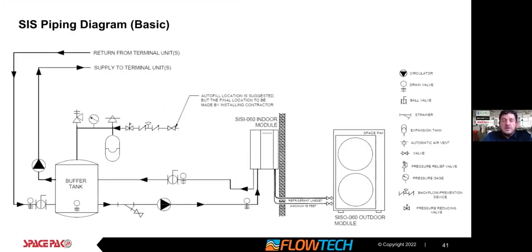Okay, we're doing good on time. So I'll spend a little bit more time on this as it's somewhat different. Similar concept with the buffer tank, but this is showing the outdoor unit and the indoor unit. And in here, you have your refrigerant line sets that come with the package. Maximum line set is 35 feet, feeding into your indoor module, and from there, water connections to the buffer tank. You will need to size a circulator for this. It's not part of the unit, so size that circulator for your system. The unit itself is 24 feet of head at 12 gallons a minute. It's a very high head situation too, so make sure you size it correctly.